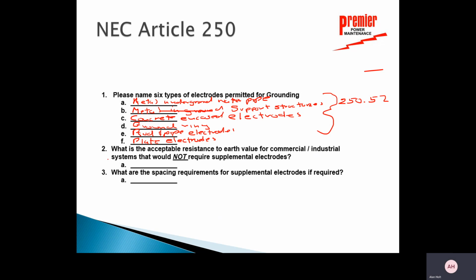So question number 2, what's the acceptable resistance to earth value for commercial industrial systems that would not require supplemental electrodes? In other words, these would pass the National Electric Code inspector, and I wouldn't have to have additional support or additional electrodes driven to the ground to try to take care of that. And that would be 25 ohms. If you're looking for that, that would be found in Article 250.53, Section A, Section 2.